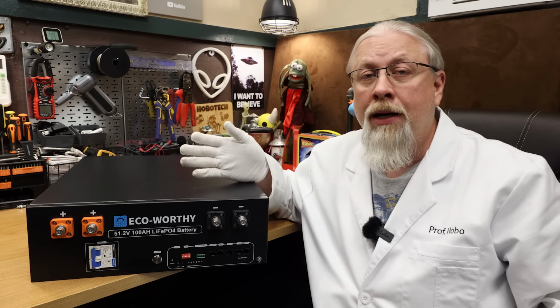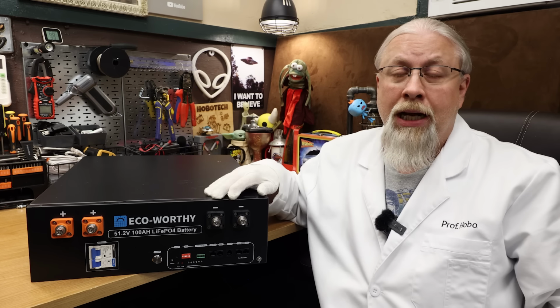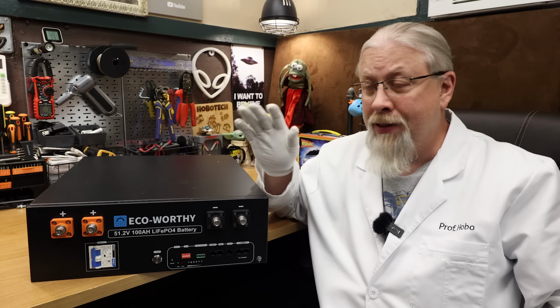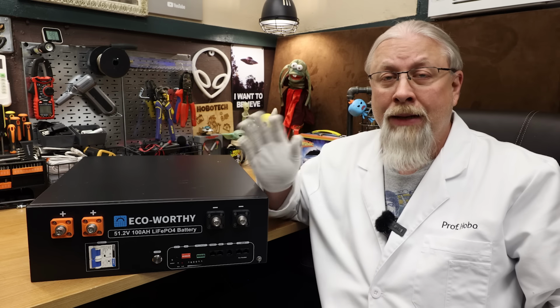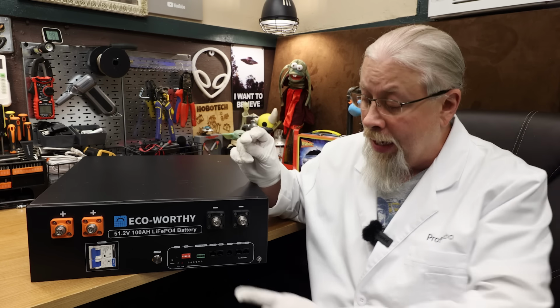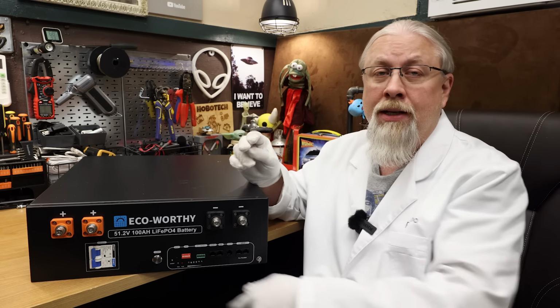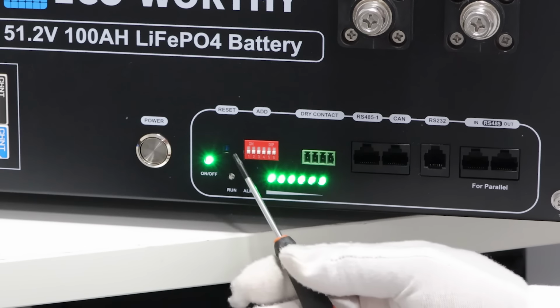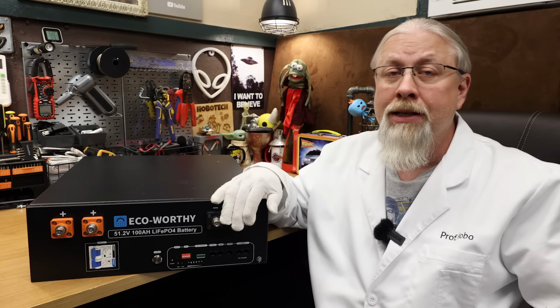As for series and parallel ability, here's where the next change was made. You are no longer limited to only 16 batteries in parallel. That limit has now been doubled by adding 2 additional dip switches in the configuration, so now you can assign up to 32 individual batteries in parallel.